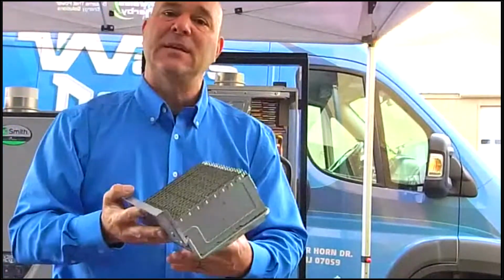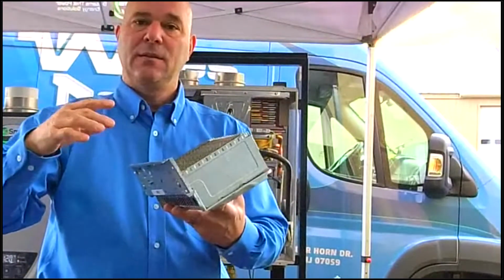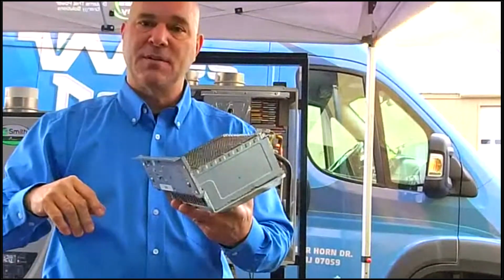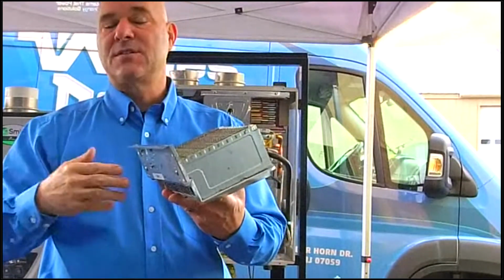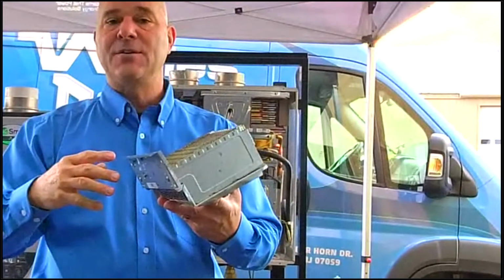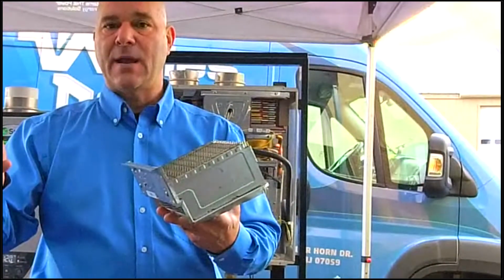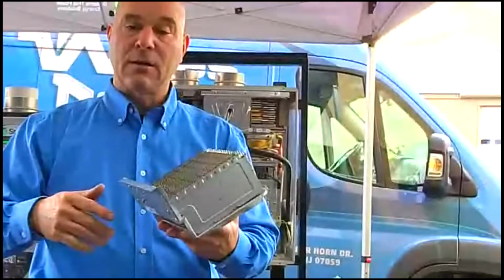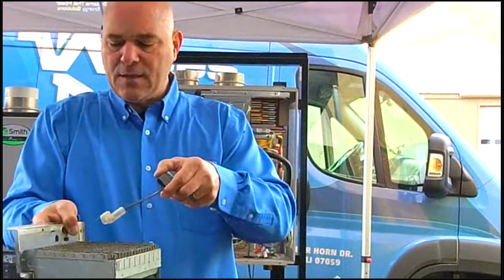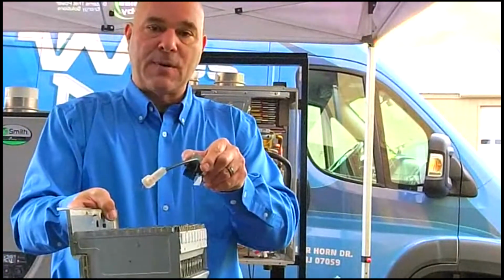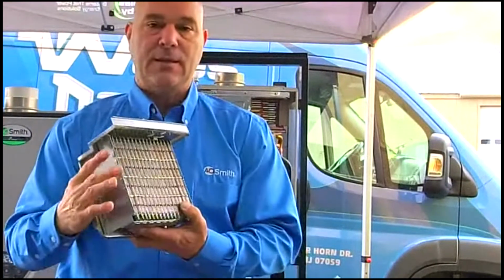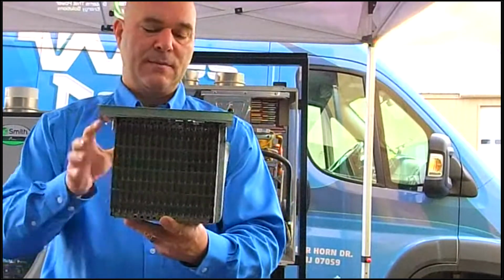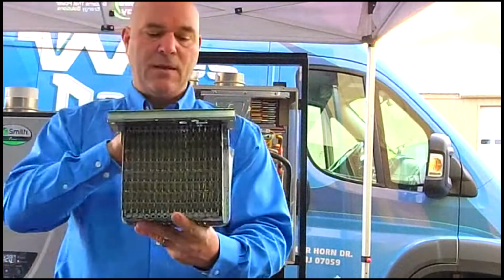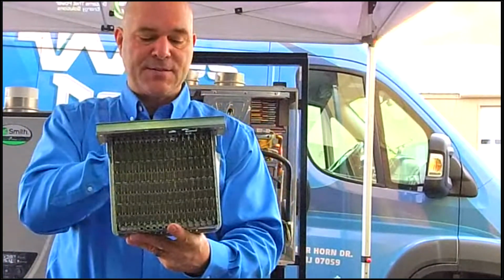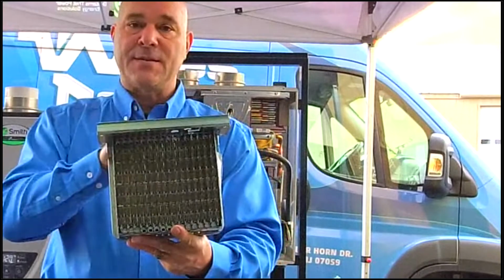If it cannot get the flame within range, say a little kid next door put a couple tennis balls into your exhaust or something, it will eventually say, hey, I can't get this flame into range, and it will shut off and give you some type of error code, probably a 111 error code or a blocked flue error code. So this igniter goes in here, it sparks directly to the burner. These are 16 individual burners. So on that gas valve setup, you have 16 gas nozzles and air nozzles on there.